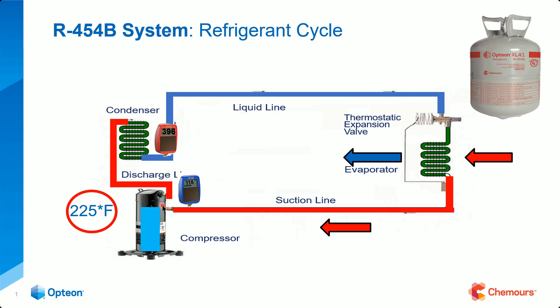Right about where that weld mark is, it's divided from low pressure to high pressure. It gets up into the scroll set — the orbiting scroll at the bottom, the fixed scroll on the top. As it starts to compress that gas, those molecules start to move a lot faster, and as they move faster it raises the heat and raises the pressure. If you've ever touched the top of a scroll compressor, you typically don't do it twice — it's pretty hot.